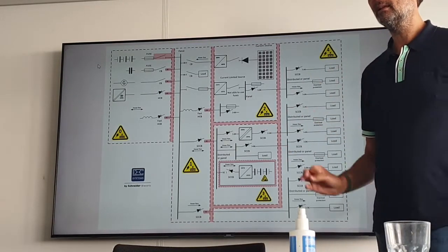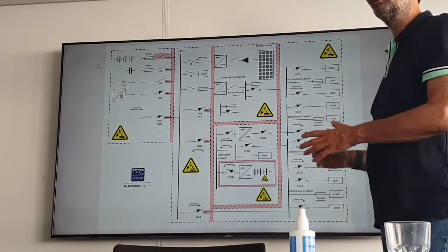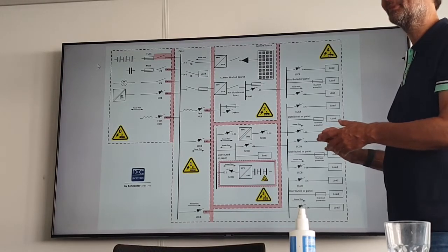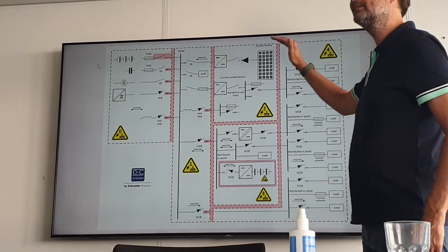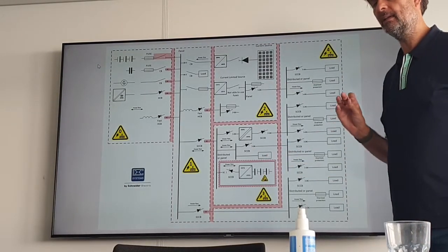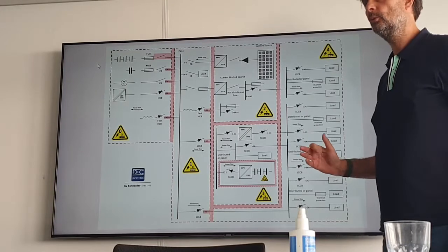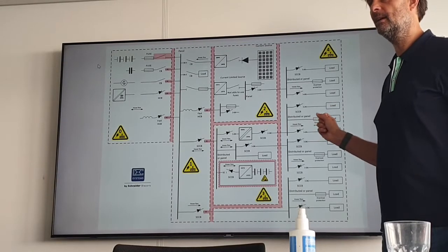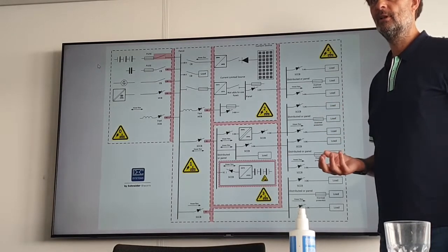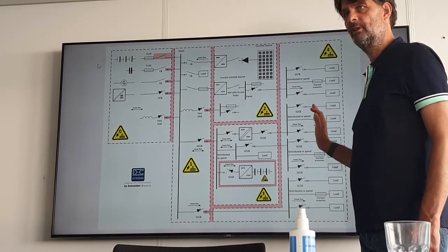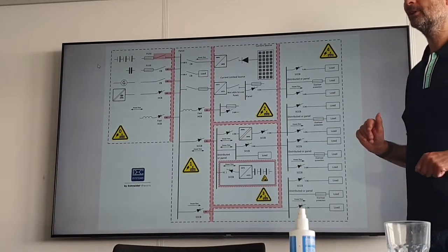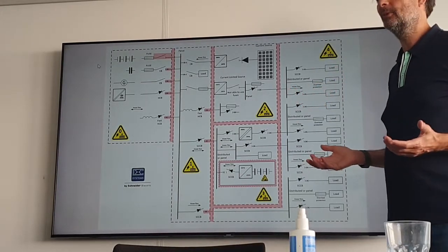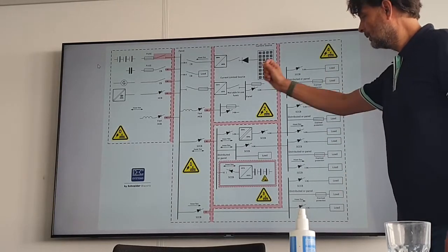So we make a table from all the requirements, and that is now the big debate in Joint Work Group 44: to get these requirements in a very conservative, strict way, to add safety to the DC installation, because DC is a very dangerous voltage, and particularly in DC, you want to call it the high voltage. People have the possibility with converters, they want to go as high as possible. Of course, you can easily go to 1500 volts, so why not? From the electronic point of view, and that's what we defined.